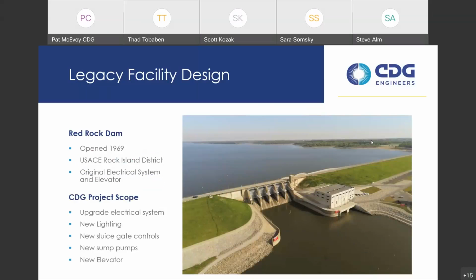So for legacy facility design, the project I'll talk about specifically is a Red Rock Dam project we had, which involved electrical upgrades to the facility. They had an original electrical system and an elevator, and part of the scope was to update that electrical system. They actually had an arc flash incident at an existing junction box supporting some raceways—an arc flash incident with some old wiring that they're not entirely sure how it started, but it was likely an exposed junction box exposed to the elements.